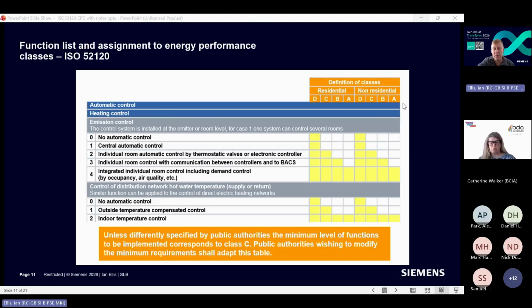If I follow that no automatic control option across the horizontal plane, the first box is coloured yellow, corresponding to the D column. So if I design a system like that to manage my heating control, my boilers for example, I'm controlling them to class D of the standard. The next one down is central automatic control.